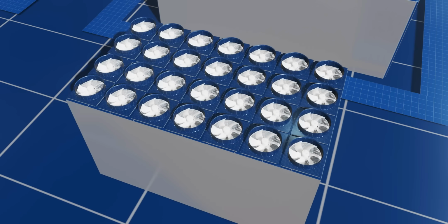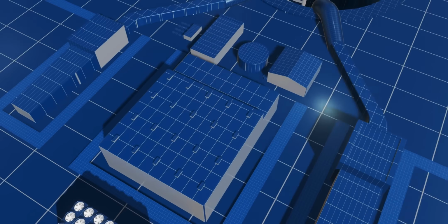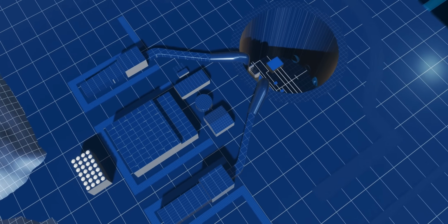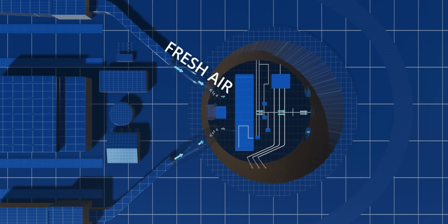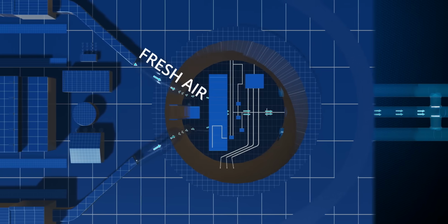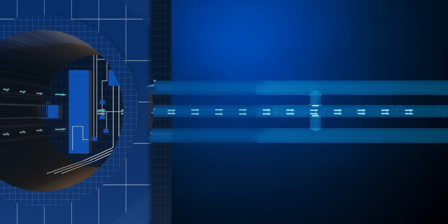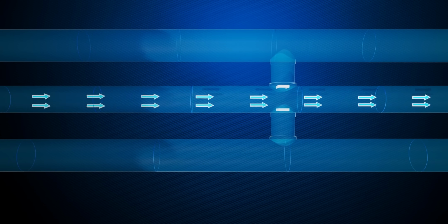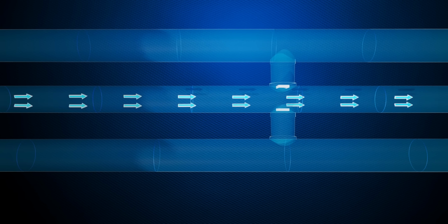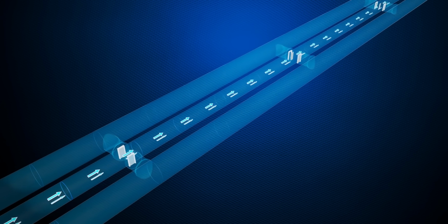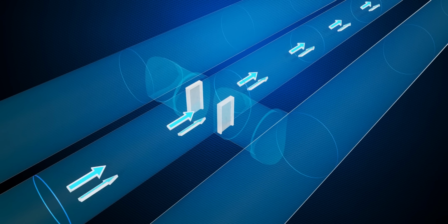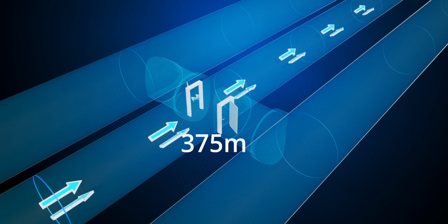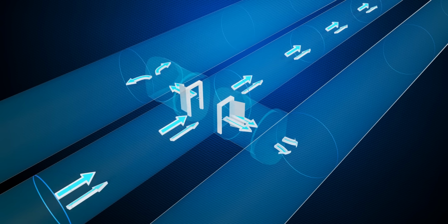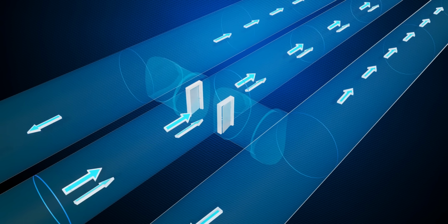You might have seen these large axial fans at the Shakespeare Cliff of the Channel Tunnel. What are they for? They supply the tunnel's fresh air. Fresh air is supplied to the service tunnel at both ends. The service tunnel is maintained at a higher air pressure than the main tunnels, and this fresh air flows into the main running tunnels through controlled louvers and doors in the cross passages. These cross passages connect the service tunnel to the main running tunnels at regular intervals, every 375 meters, and are equipped with doors that can be opened and closed to control airflow.